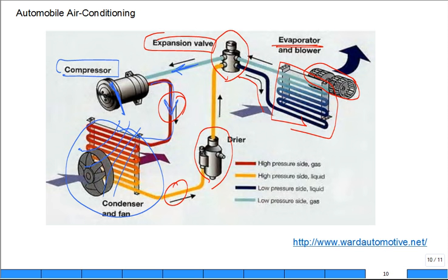All right. So this is a very interesting device. They have a number of them. Here, I'm going to pass this one around. I show students in Thermo 1, but you have two ins and two outs, okay? So this passage through this way, it basically senses the temperature of the refrigerant leaving the evaporator, and there's a bulb right in the middle, okay? That's not to block the flow, but to sense the temperature of the flow going through it. Now, that is nice and big, and it's gas in there, and it helps expand when it's warm and contract when it's cold. And it's connected to a diaphragm, which accentuates the expansion and contraction.